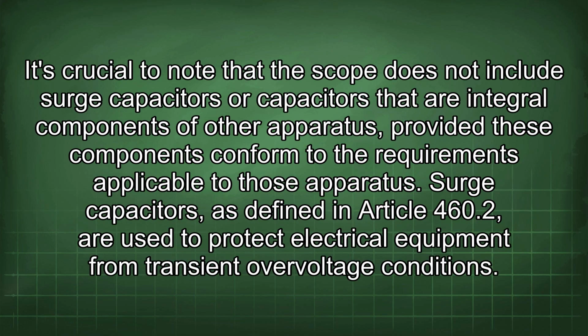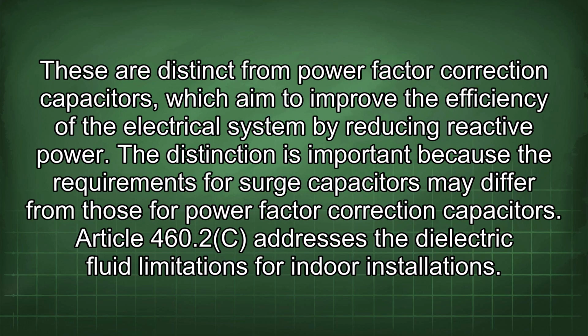It's crucial to note that the scope does not include surge capacitors or capacitors that are integral components of other apparatus, provided these components conform to the requirements applicable to those apparatus. Surge capacitors, as defined in Article 460.2, are used to protect electrical equipment from transient overvoltage conditions. These are distinct from power factor correction capacitors, which aim to improve the efficiency of the electrical system by reducing reactive power. The distinction is important because the requirements for surge capacitors may differ from those for power factor correction capacitors.